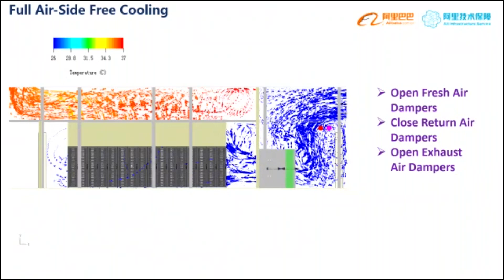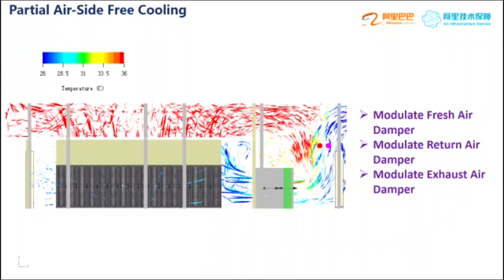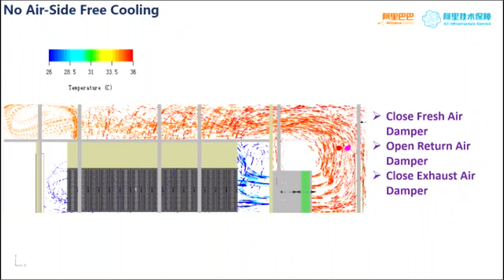When the air temperature is fit for direct air-side free cooling, the control system opens fresh air dampers, closes return air dampers, and opens exhaust air dampers. When the enthalpy of fresh air is less than return air, the intelligent system needs to switch the cooling system into partial air-side free cooling. At the same time, it modulates fresh air, return air, and exhaust air dampers. When air quality is bad or temperature is high, the intelligent system needs to switch the cooling system into no air-side free cooling: close the fresh air damper, open the return air damper, and close the exhaust air damper. All the switches should be seamless.